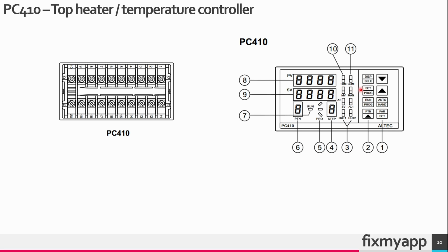for adjusting the settings. This is the front side of this temperature controller and this is the back side of the temperature controller. In part 3 we will dive deeper into this temperature controller, how to set it up, how to calibrate it and also do some test runs. On the back side these are the terminal connections, so this is terminal 1 to 10 and this 11 till 20 and the wires will be connected to these terminals.